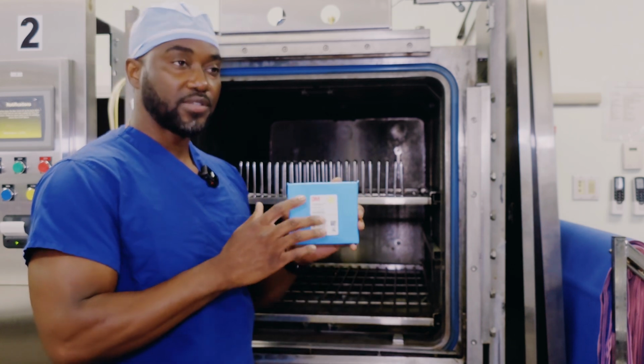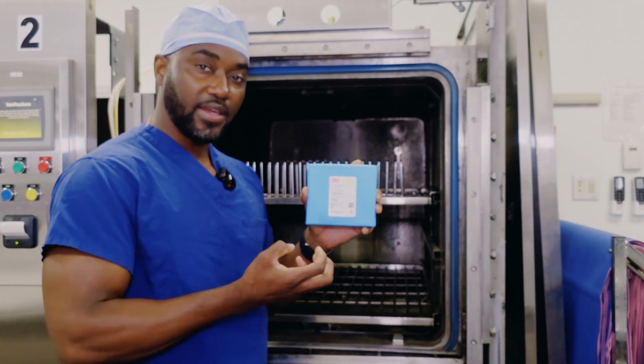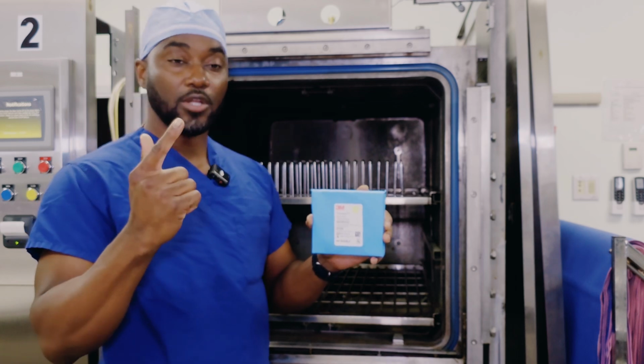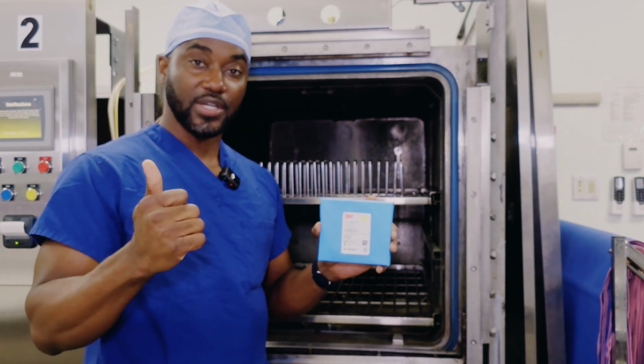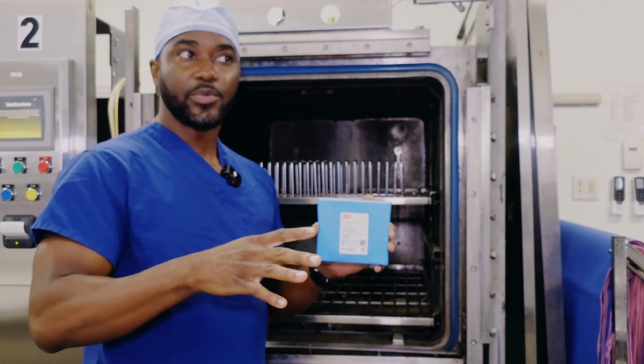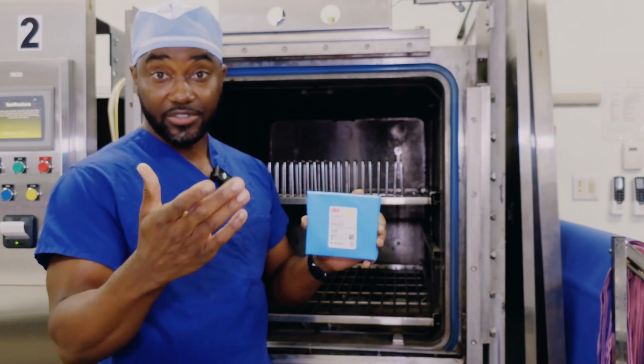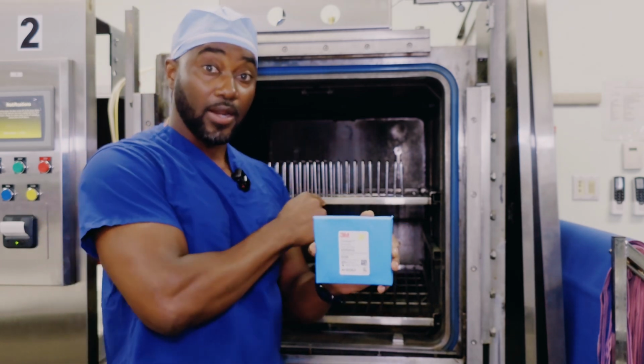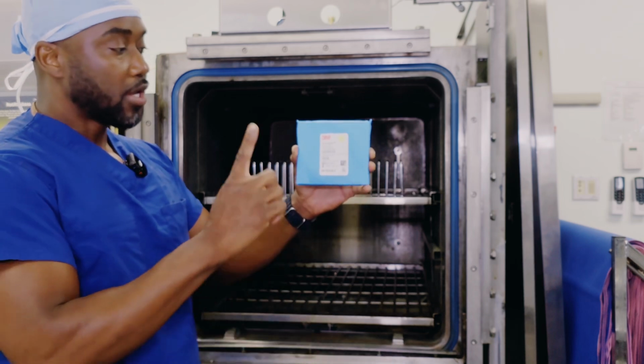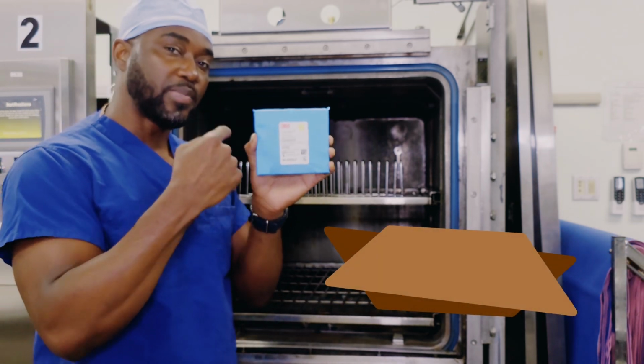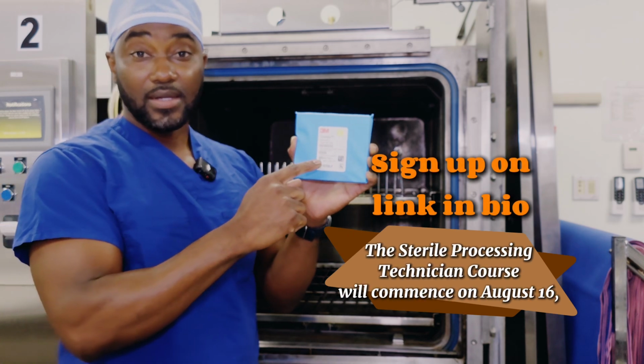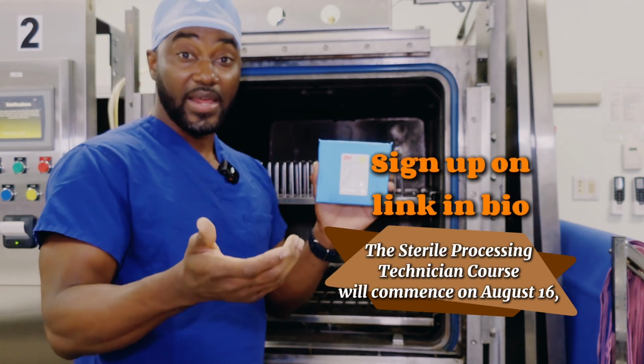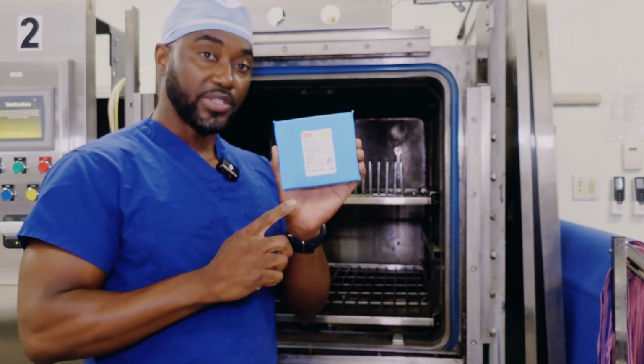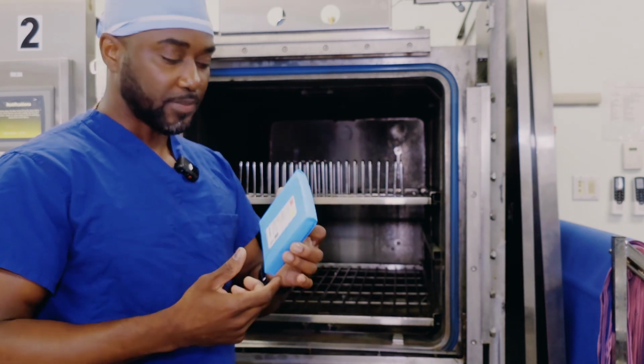This test is done to check the exhaust of air from the autoclave. We use this test to find out if our autoclave is sucking air out. So the first load you run in the morning for your sterilization cycle, or if you work in a hospital, the first shift that works overnight, every 24 hours before any load is run on this pre-vacuum sterilizer, you have to run your Bowie-Dick test. This Bowie-Dick test is produced by the company 3M. You might have other Bowie-Dick test class 2 chemical indicators manufactured by other manufacturers. We use the 3M Bowie-Dick test, and this is an air removal test.